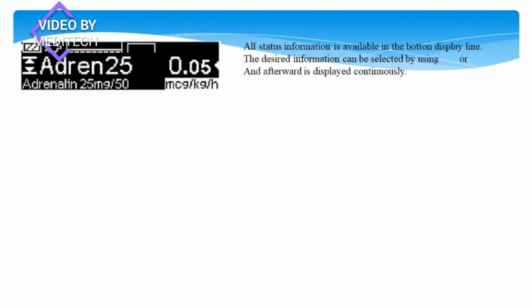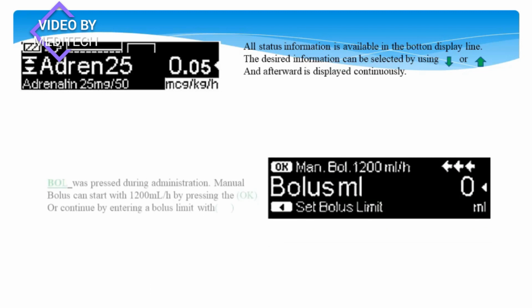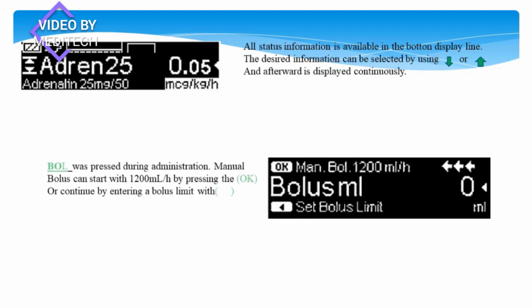This display: all status information is available in the bottom display line. The desired information can be selected by using the down arrow or up arrow, and afterward is displayed continuously. Bolus was pressed during administration. Manual bolus can start with 1200 ml per hour by pressing the OK button, or continue by entering a bolus limit with the left arrow button.